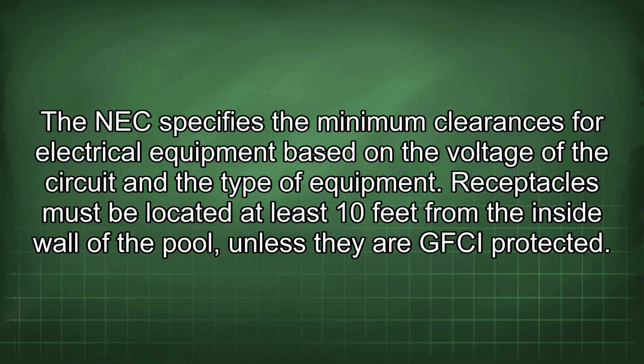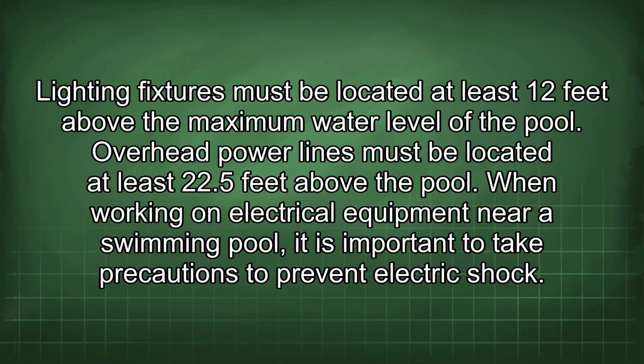Receptacles must be located at least 10 feet from the inside wall of the pool, unless they are GFCI protected. Lighting fixtures must be located at least 12 feet above the maximum water level of the pool. Overhead power lines must be located at least 22.5 feet above the pool. When working on electrical equipment near a swimming pool, it is important to take precautions to prevent electric shock.